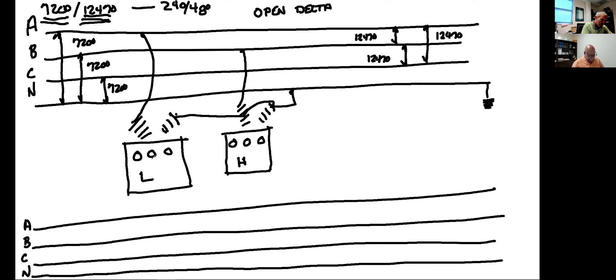We know in delta, remember, this is the lighting transformer, and this is the high leg transformer. On the lighting transformer, we have the center bushing. It goes to where? Neutral, and this neutral is grounded. Bang, bang, bang. This is 240, 480. I haven't drawn them in yet, but I can go ahead and draw my lines in. Make this kind of simple for myself.